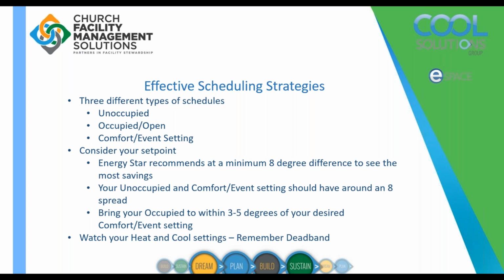And then that allows you to take advantage of that lockout feature that many thermostats have, which allows anybody to come in if they forgot to schedule the room. I know that happens very, very seldom in the church world. Everybody is always good about getting everything on the calendar. However, for the time that it happens that they don't, if we've got our occupied setting within 3 to 5 degrees and we allow a 4-degree adjustment, they can go into the room, hit that thermostat, and for 1 or 2 hours they can adjust that temperature themselves.